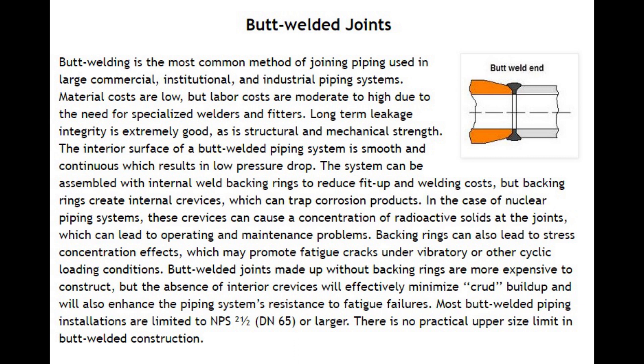Number 1: Butt Welded Joints. Butt welding is the most common method of joining piping used in large commercial, institutional, and industrial piping systems. Material costs are low, but labor costs are moderate to high due to the need for specialized welders and fitters. Long term leakage integrity is extremely good, as is structural and mechanical strength.